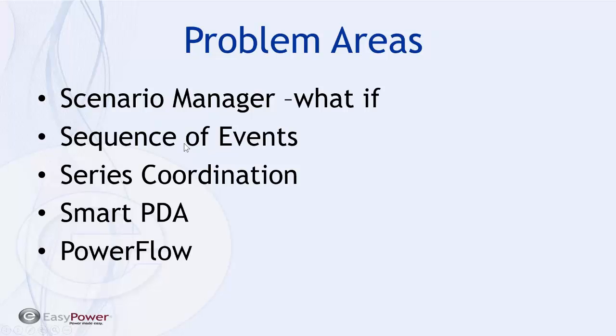If we're looking for miscoordination, the sequence of events utility built into the coordination module is extremely valuable for a first look at whether we have a gross misadjustment of breakers, or if it's isolated to only one or two buses. We'll be covering that at a later refresher.